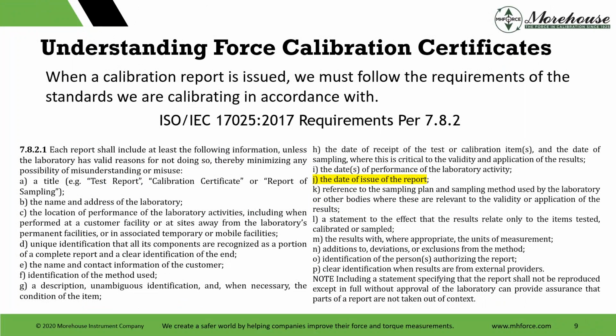First is understanding the requirements of ISO/IEC 17025:2017, found in section 7.8.2. These are all the things we have to follow when a calibration report is issued. We had an audit and had one deficiency: we missed the date of issue of the report. We went over everything, and yet we still missed that one thing.